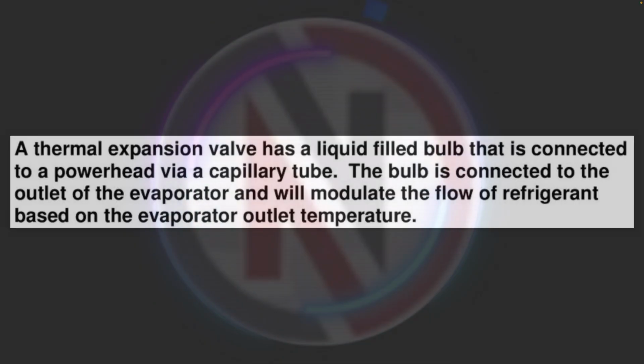B. TXV. A thermal expansion valve has a liquid-filled bulb that is connected to a power head via a capillary tube. The bulb is connected to the outlet of the evaporator and will modulate the flow of refrigerant based on the evaporator outlet temperature.